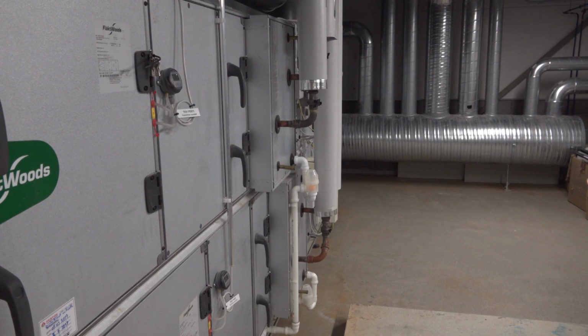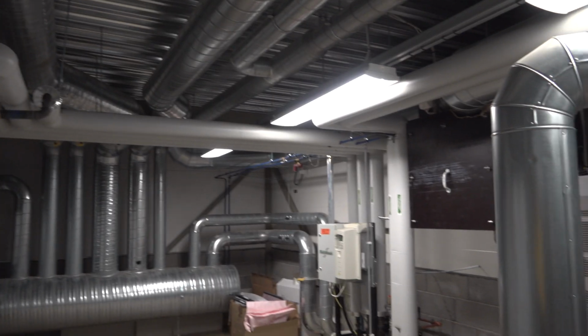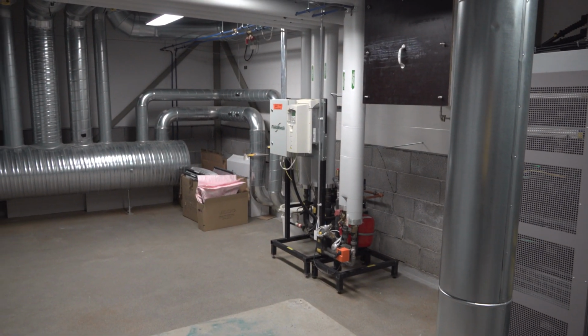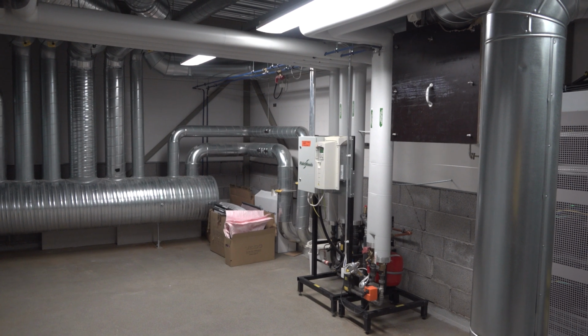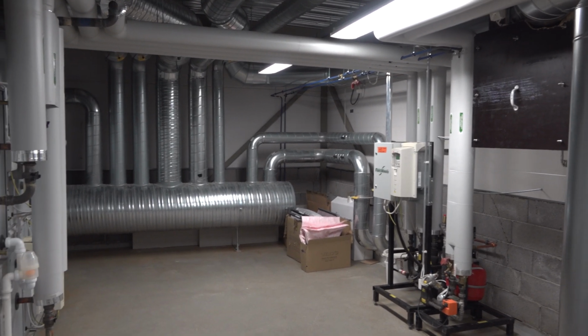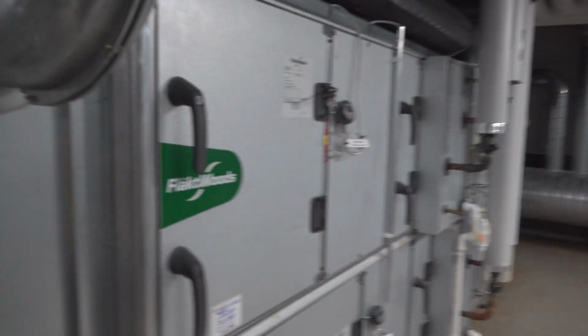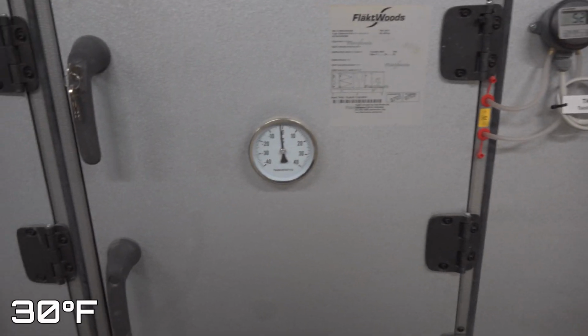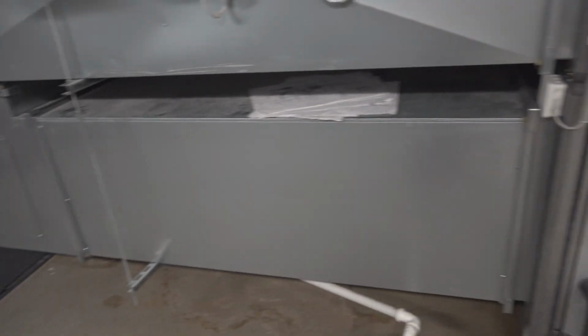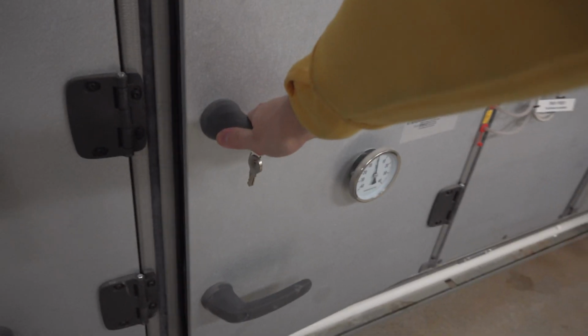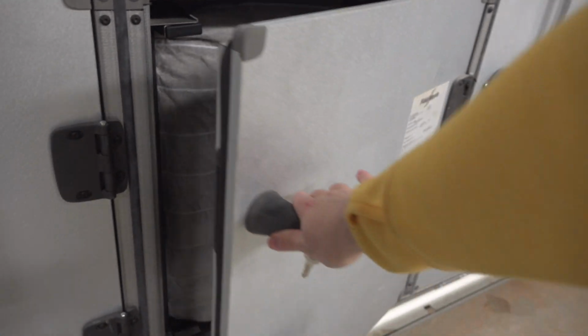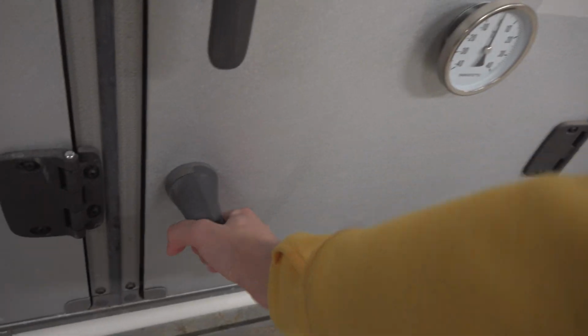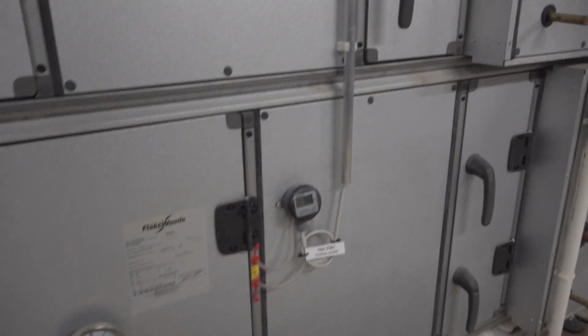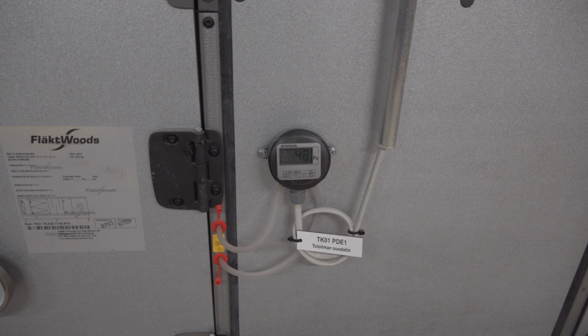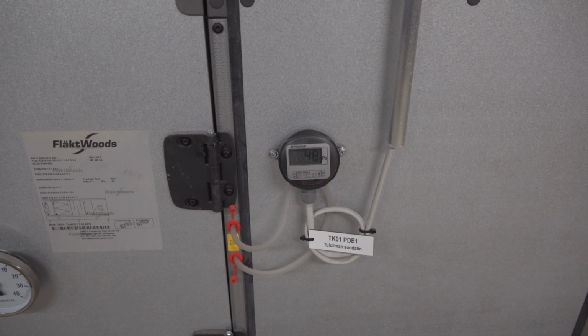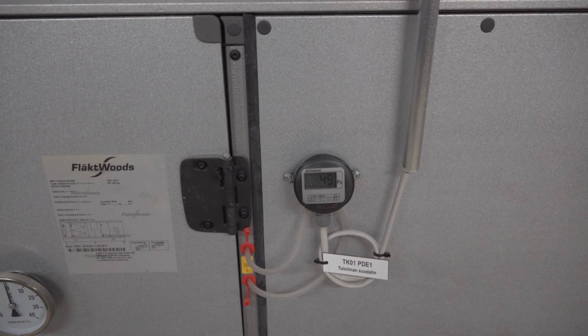Here you can see the two heat exchangers with the loop to the motor connecting them. The loop is filled with ethylene glycol and water mixture, which keeps it from freezing because the air temperature in the input side can drop below zero, which currently it is. On the input side, you can see there are bag filters here, which take dust and pollen out of the air. And then there is a pressure gauge before and after the filter to measure the pressure drop over it to figure out how clogged the filter is.